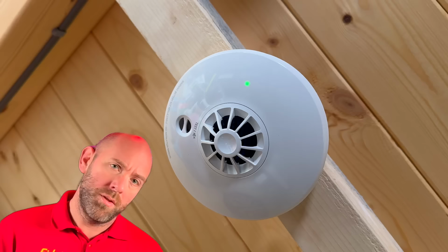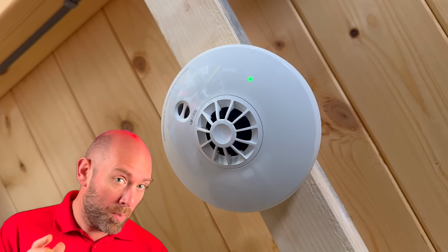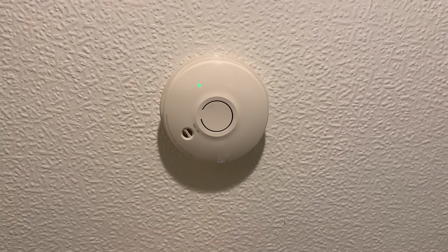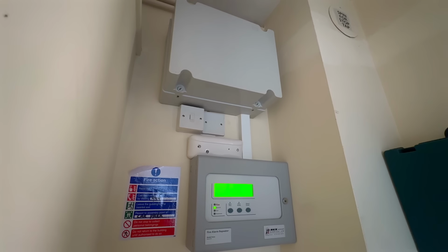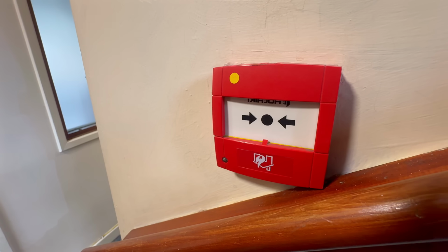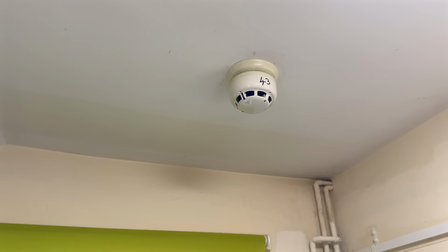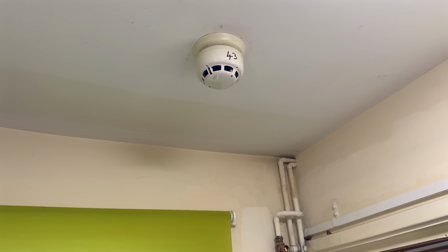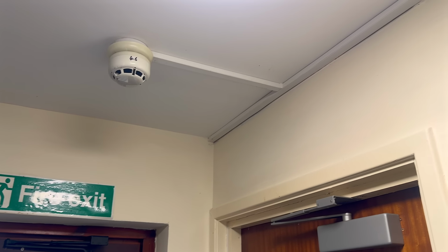Okay, so let's get into this, starting with grade and life protection, as these do fall across both volumes of Part B, and we're going to start with grades. The grade tells you how a system is powered and how it operates as a system. The grading does not tell you where the detectors are installed. It only defines the system architecture. Grade A is a full fire alarm system with a control and indicating panel, manual call point and separate detectors. Grade C uses detectors and sounders powered from a central power supply, but without a full control panel.